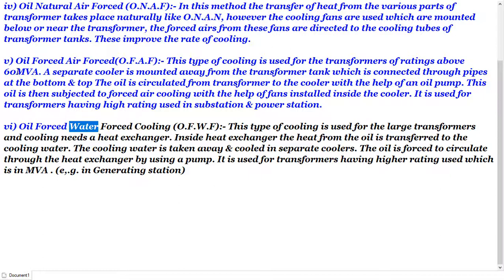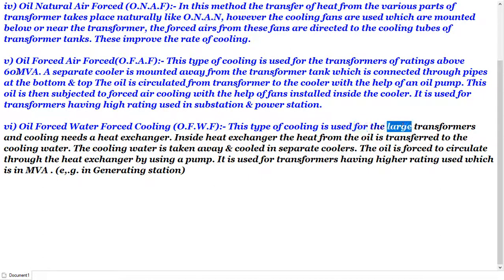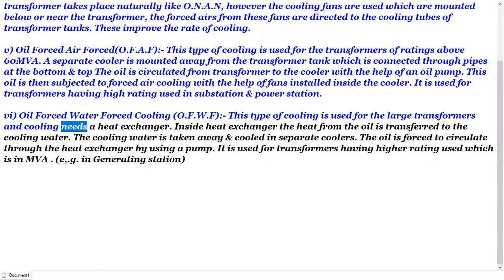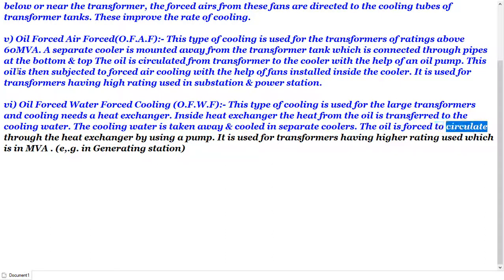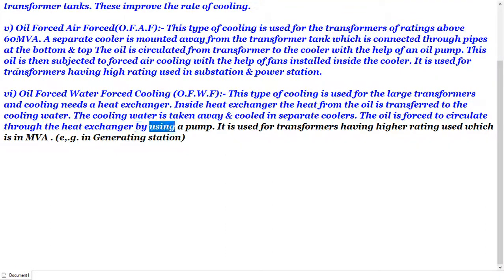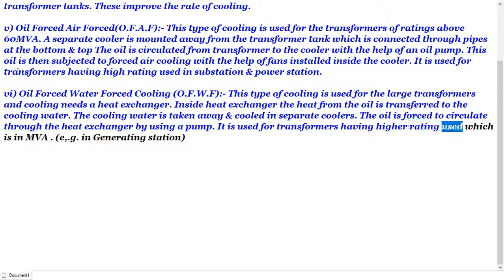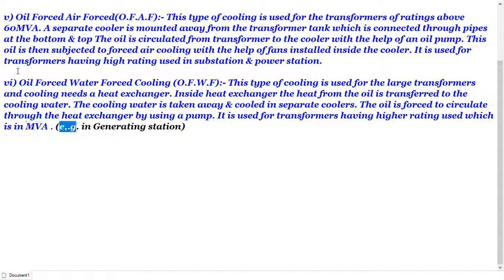6. Oil Forced Water Forced (OFWF): This type of cooling is used for large transformers and requires a heat exchanger. Inside the heat exchanger, the heat from the oil is transferred to the cooling water. The cooling water is taken away and cooled in separate coolers. The oil is forced to circulate through the heat exchanger using a pump. It is used for transformers having higher MVA ratings in generating stations.